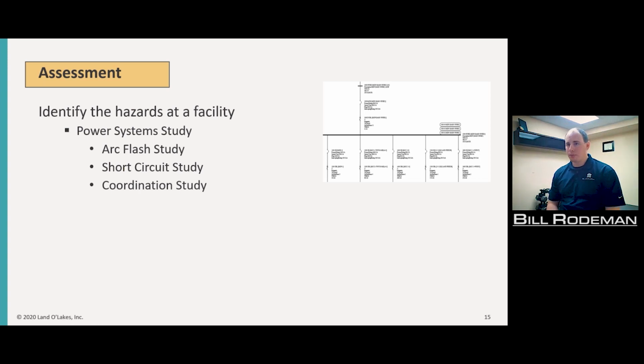When you're looking at the arc flash study or the incident energy analysis, it's going to say, okay, for each piece of equipment in my system, if an arc flash happens there, here's how much energy is going to be released, and here's how far away you need to stand in order to not be burned. When you're looking at the short circuit study, if I have a piece of equipment and a fault happens there, how much current is actually going to hit that piece of equipment, worst case scenario. And so you're going to need a lot of that information, or at least how much current's available for your arc flash study.